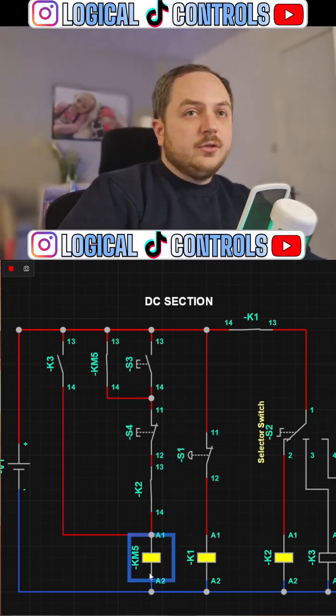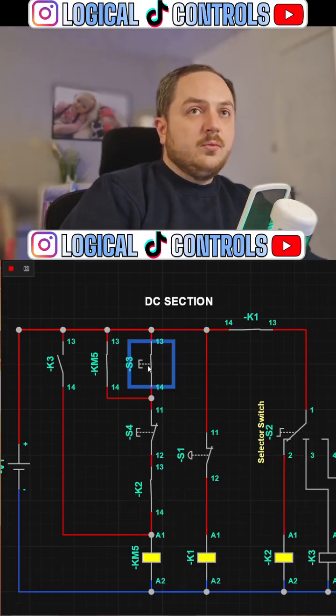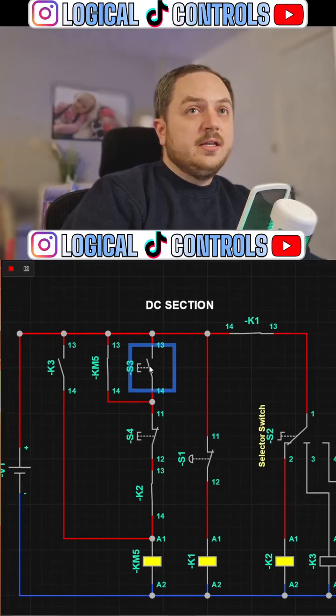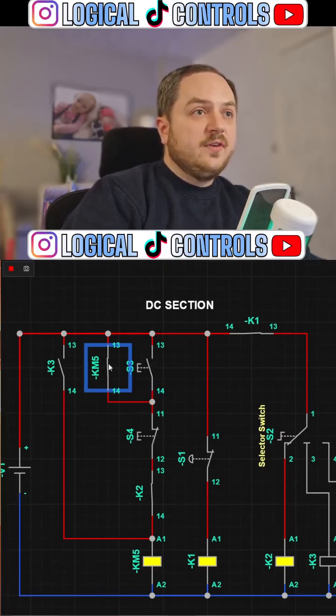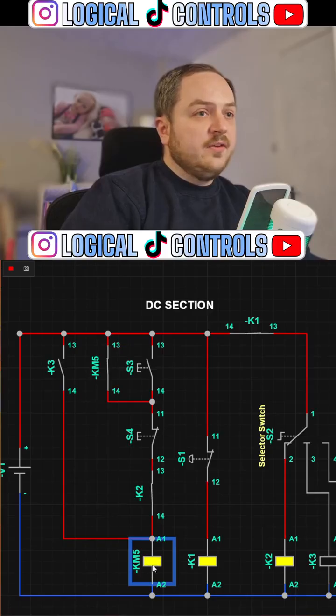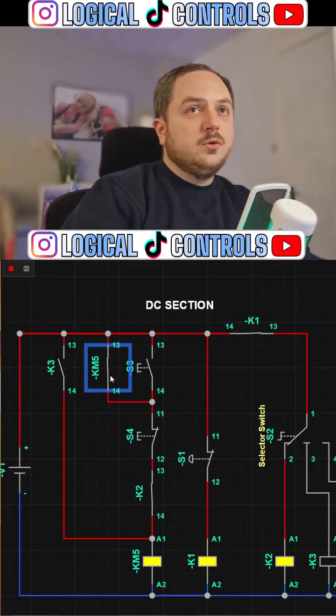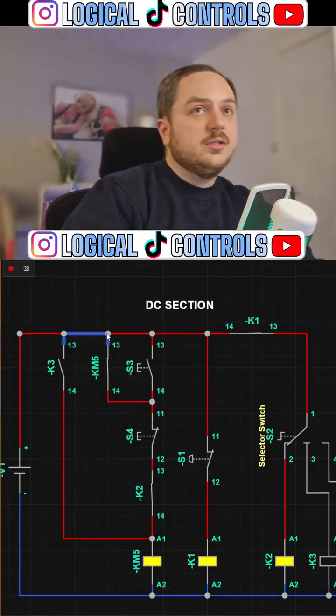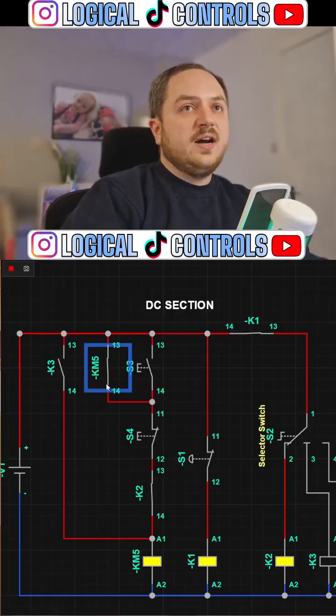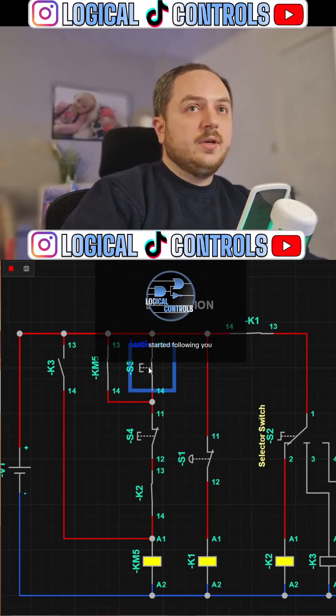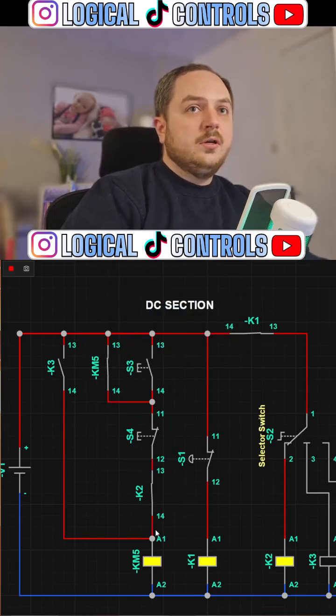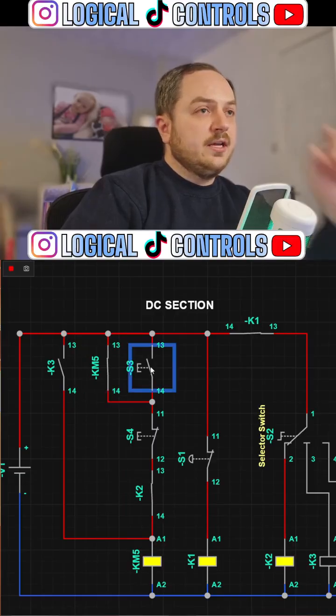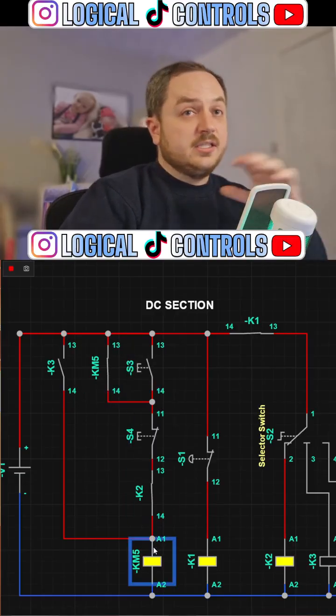Yeah, we go through K2 and it energizes KM5. So we just momentarily pressed S3, it closed momentarily. The minute I let go, if this KM5 contact here wasn't there, KM5 would just de-energize. So this is what's called a latching circuit, or holding circuit - other people call it that because KM5, which is a contact of itself, is holding it in. Basically, when you press that start button and let go, KM5 energizes very quickly and closes on itself, so when you let go of the start button, it stays energized.